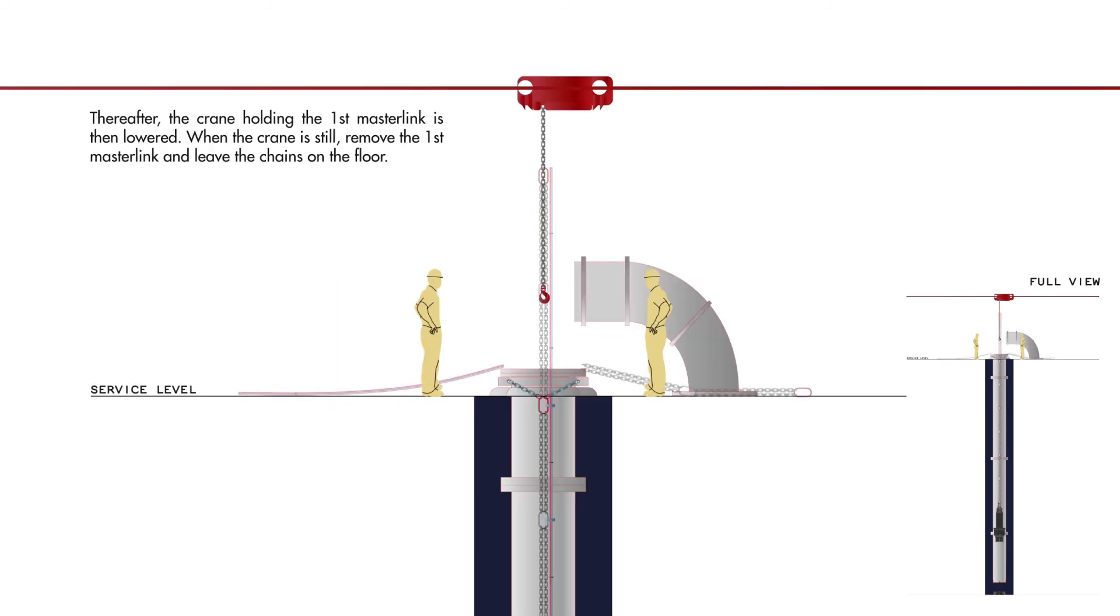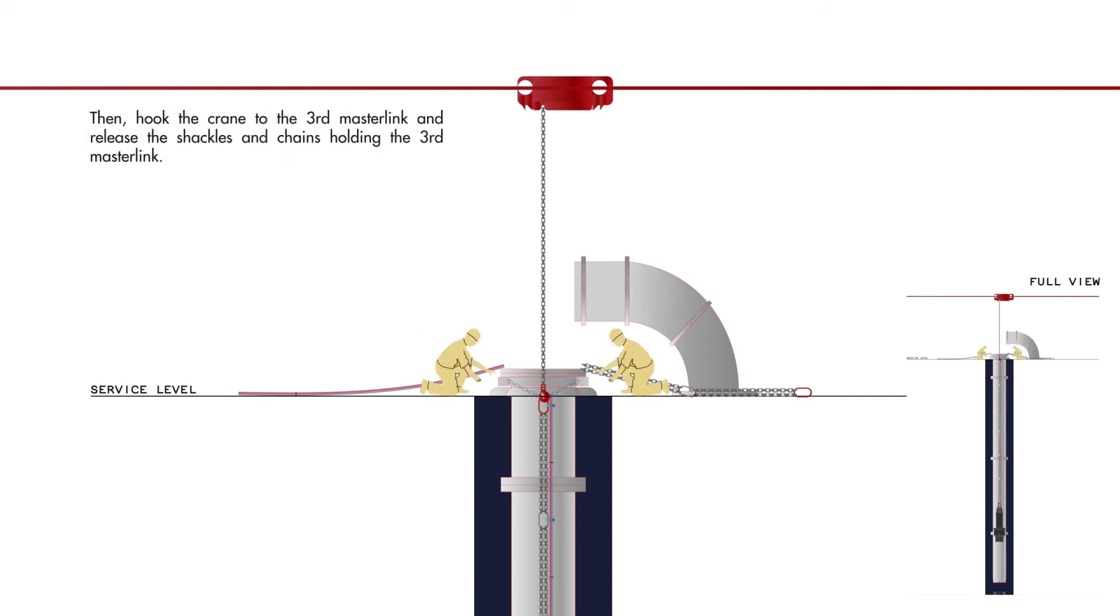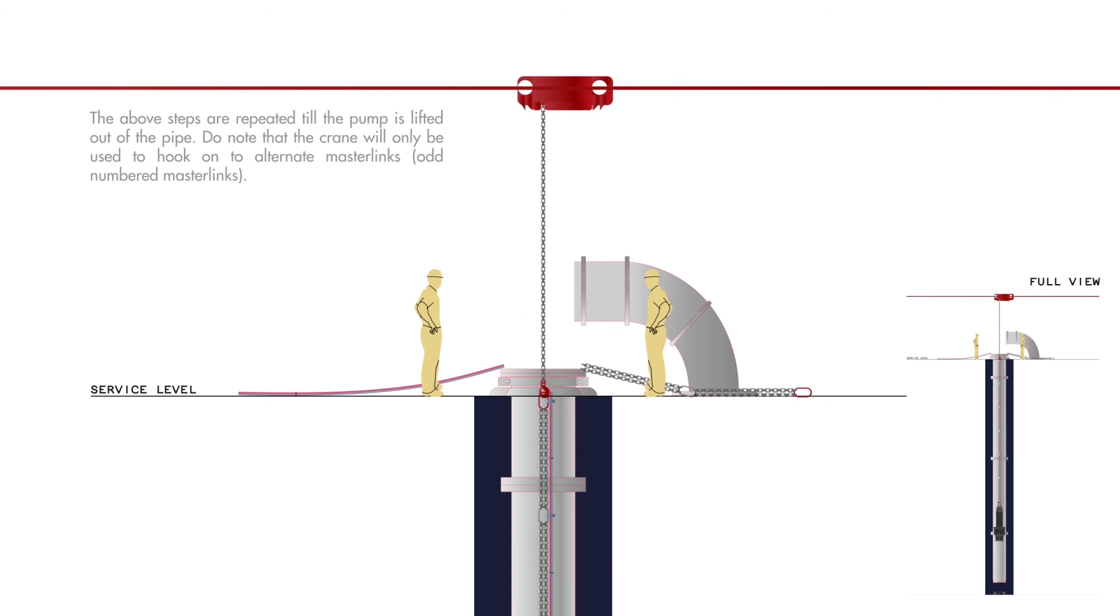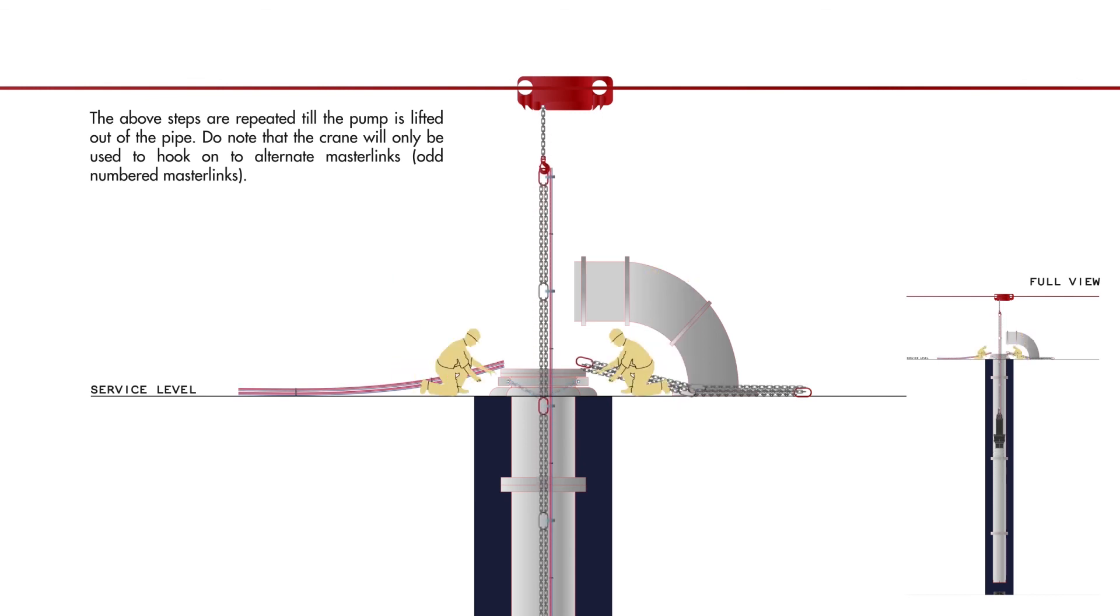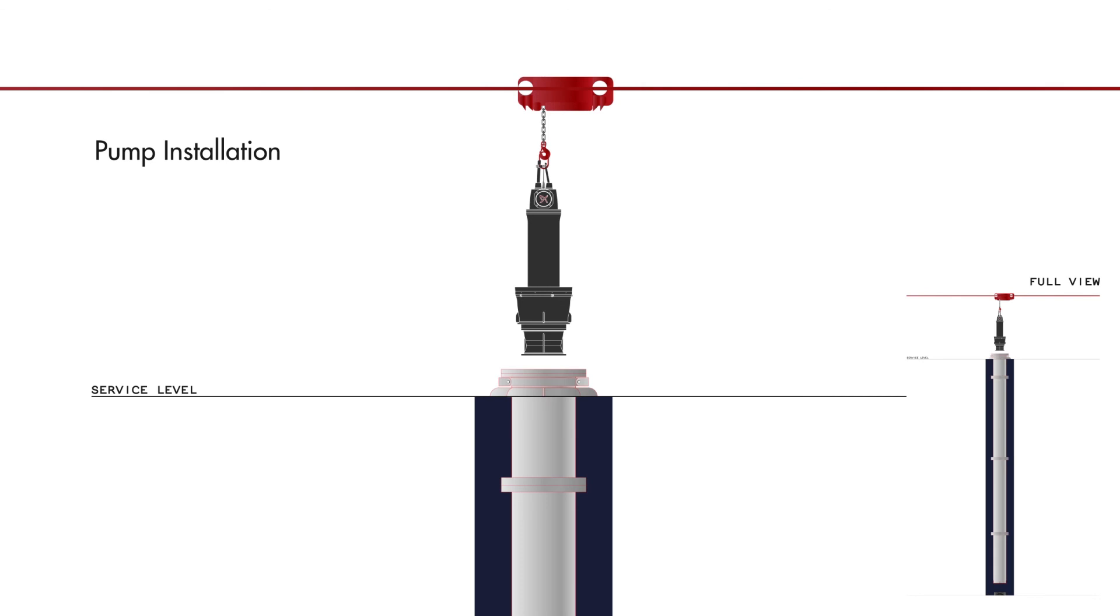To lift up the pump from the column tube, hook onto the first master link and remove the turnbuckles. Start to lift the pump up as high as possible and install the support chains in the closest possible master link. Hook onto that master link with the hook and repeat the process until the pump is free of the column tube.